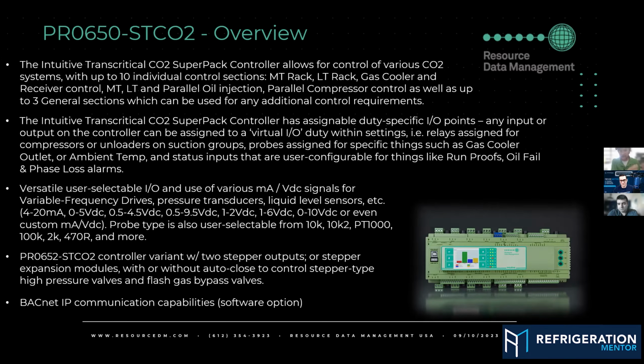You got to understand that there's a lot to it and a lot that goes on. It's not just controls. You also have to look at the mechanical side of things too. And so what happens is this time delay is set for 10 minutes and it doesn't see that signal come back, it's going to continue its cycle and so on and so forth. And then I get a lot of calls on just racks not fine tuned. Cases are flooding out. Cases never got checked right. You've got iced up compressors. CO2's a cold refrigerant. It is what it is. And if this isn't set right, now we've got flood back. Now you've got your flash gas valve going all over the place hunting. And then you've got your high pressure hunting all the time. The gas cooler was never set up correctly. I get a lot of that going on, and it's like, okay, let's take it one step at a time, and we'll start here, and then we're going to move on down the line.